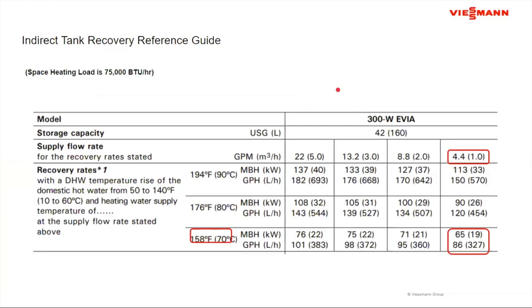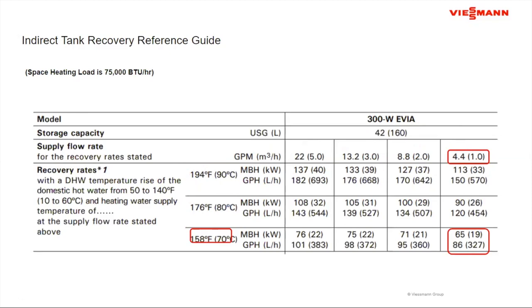Now, on the domestic water side, the other thing I have to figure out is how do I set this up to perform? Because when we look at domestic hot water performance, it's about BTUs, it's about gallons per minute, and it's about water temperatures. Most manufacturers, when they have an indirect, you'll see charts like this. This happens to be that 42-gallon tank we're looking at. So here are flow rates: 4.4 gallons, 8.8 gallons, 13.2 and 22 gallons. Water temperatures: 158, 176, 194. I'm looking for 51 gallons, first hour.